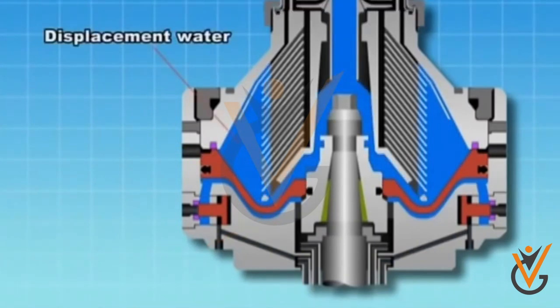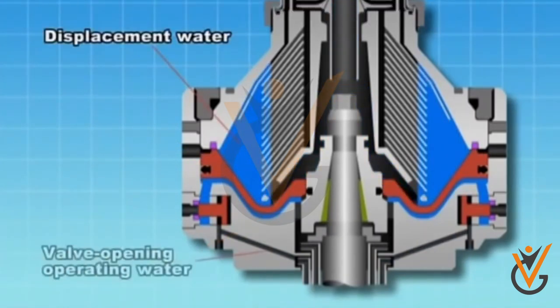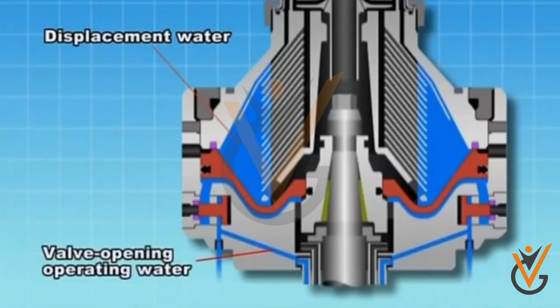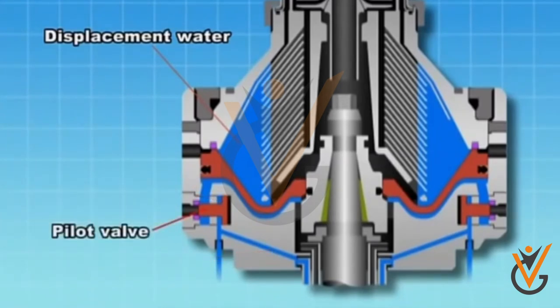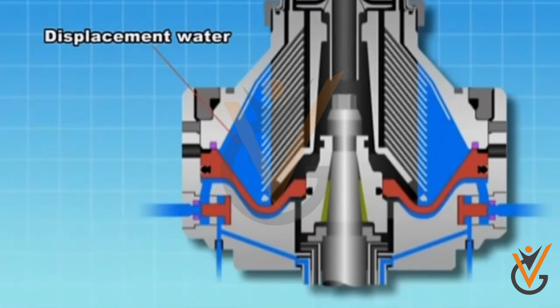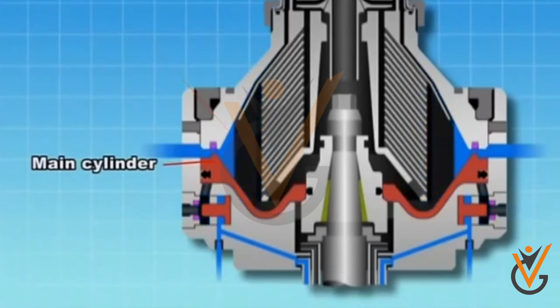Displacement Water: Before the desludging, there is oil inside the purifier. So we simply provide the water through the additional water to the purifier, so that the oil will lift up to the service tank and hence there will be no wastage of oil at all and purifier will be left with the only water before the desludging.